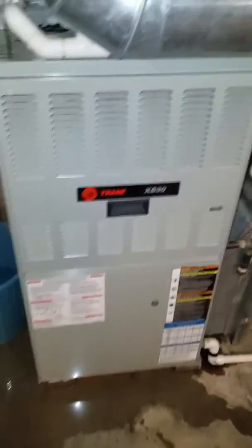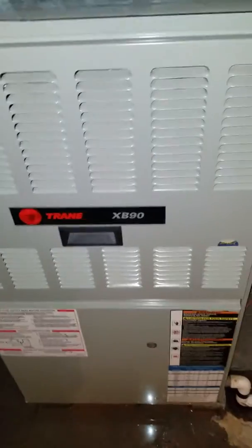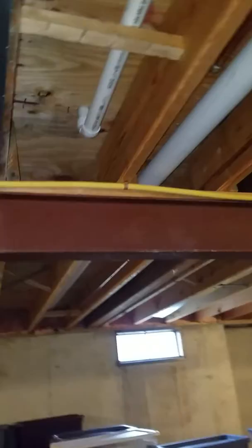They're looking at a 100,000 BTU Trane XB90 furnace. There's a 3-inch flue that runs all the way down, turns, and runs through the back of the house. About 25 feet here, another 25 feet — so about 50 feet of PVC.